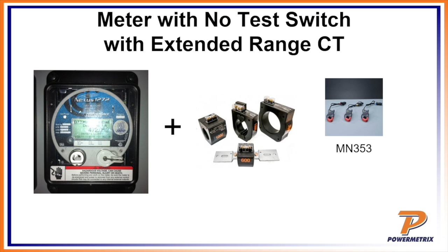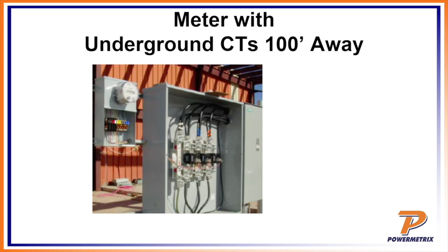So what if I had a meter with underground CTs that's a pretty good distance away, like 100 feet? Okay, so we've got a meter with underground CTs. If they were overhead, we would know immediately what we had to use, right? Not necessarily. If it's overhead at 600 volts or less, we could use a flex or a HighVolt probe. But if it's overhead and over 600 volts, we would have to use the HighVolt probe. In this case, since he said underground CTs, he's probably going to be using flexes, and he's going to need extension cables to get out there.